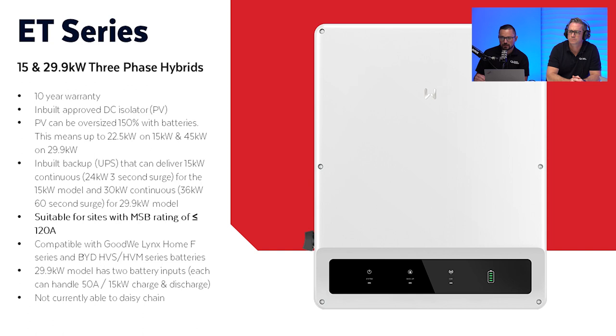If you're using at the moment a 10 kilowatt three phase hybrid and paralleling these together, typically that'll mean you're realistically limited to about 3.3 kilowatt per phase of backup ability, which doesn't quite cut it in a lot of cases.